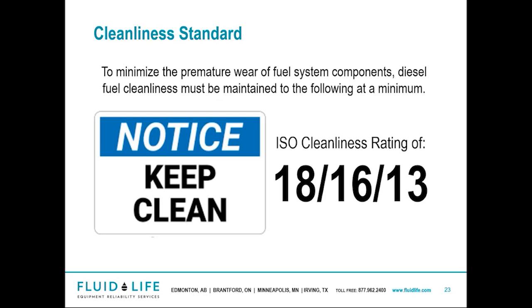Okay, similar to that 500 parts per million water threshold in terms of allowable water content or maximum water content, OEMs and that ASTM D975 guideline, they also have a maximum cleanliness rating. So for this, you'd have to be familiar with ISO codes, but 18/16/13 is pretty much the maximum. And that is what we start flagging cleanliness at, and that's what the majority of your OEMs would give you in terms of maximum fuel cleanliness, maximum being the dirtiest allowable fuel.